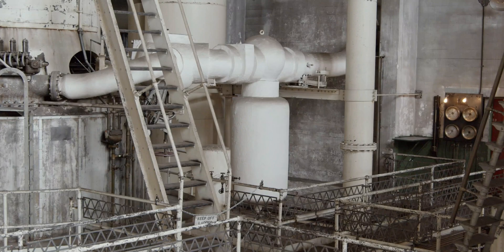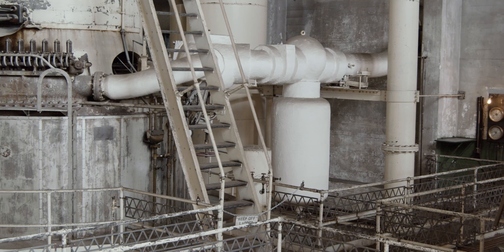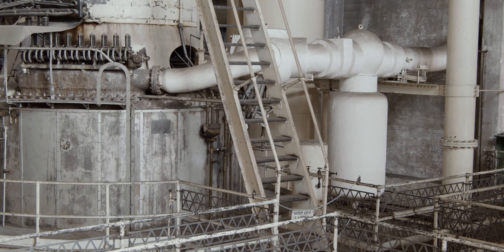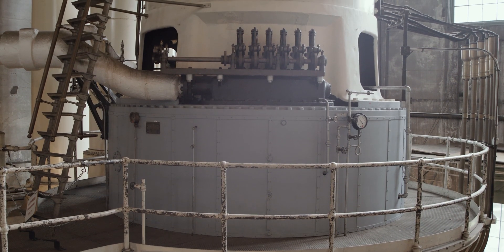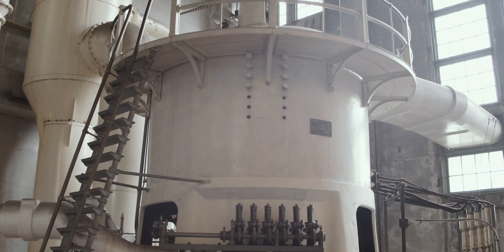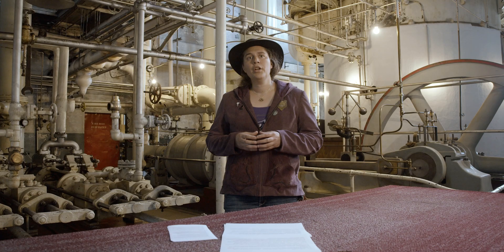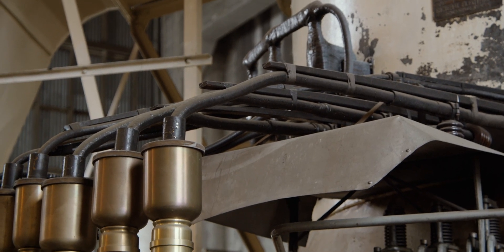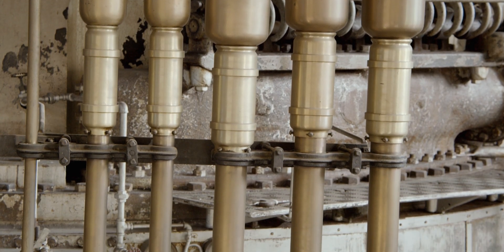For both units, you can see the steam turbine part on the bottom of the unit. The steam enters the turbine through the white pipe at approximately 175 psi. In the middle of the unit is the oil-supported step bearing. And then on top of the unit is the generator unit itself. You can see where the wires for the generator leave the generating unit and come down the beautiful brass pipes on the side of the unit.